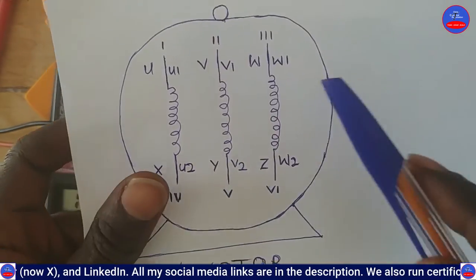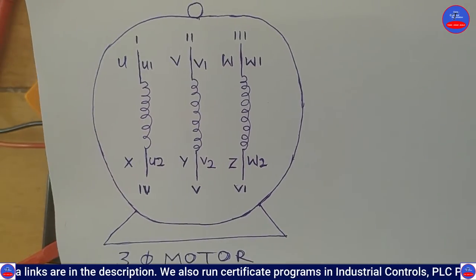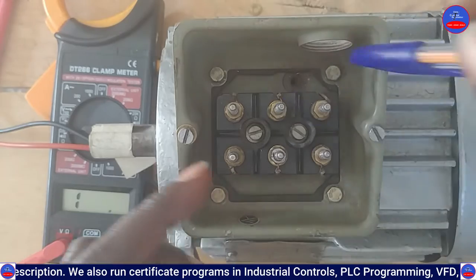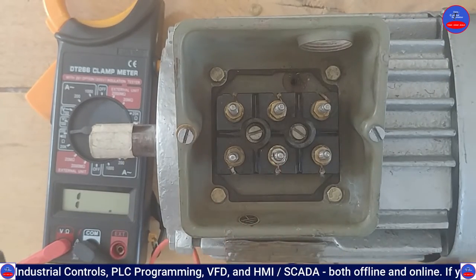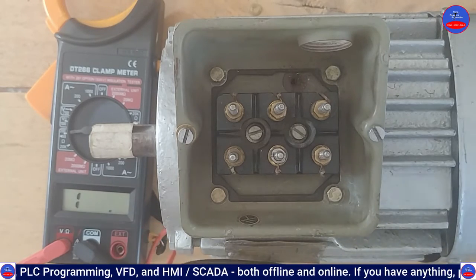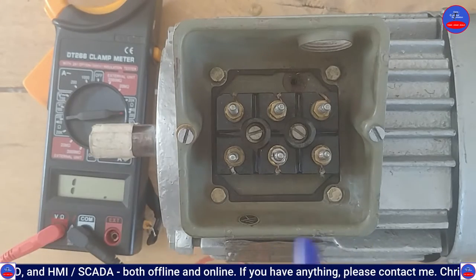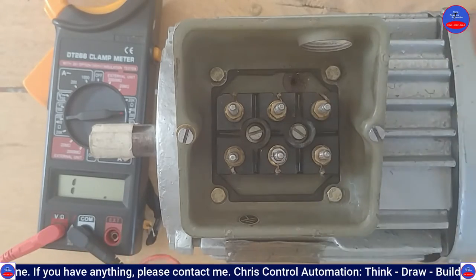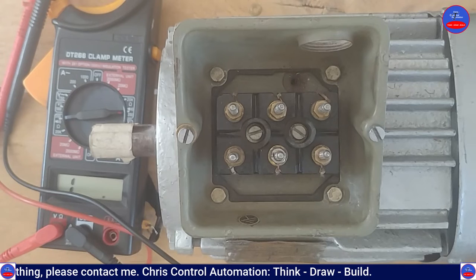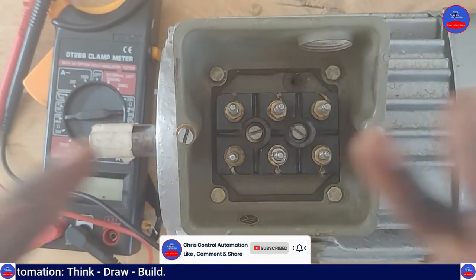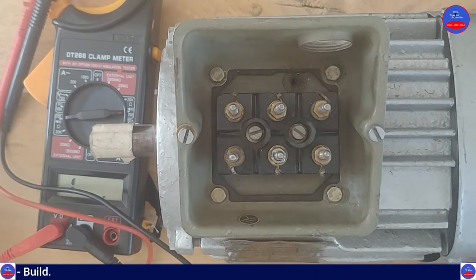So any markings you find on motor terminal blocks, you should be able to identify the corresponding winding terminals. That was a simple continuity test on our three-phase motor to identify the corresponding windings. I would advise that when doing the insulation test between windings and body, make sure you use a high-resistance instrument — a megger or insulation resistance tester. This multimeter is also accepted, but if you are not sure, use an insulation resistance tester. I'll be talking about that in my next video. Please subscribe to this channel, hit the bell icon, like the video, leave your comments, and share with your friends. Let's meet in another video — thank you.